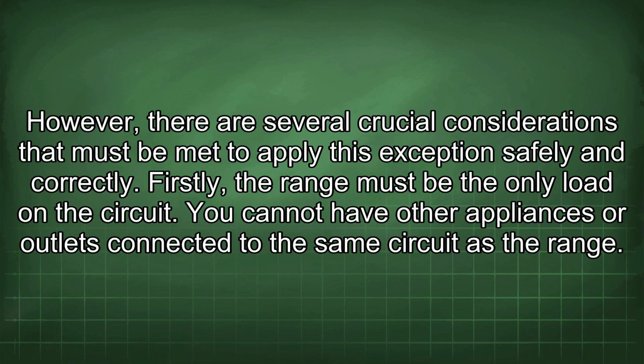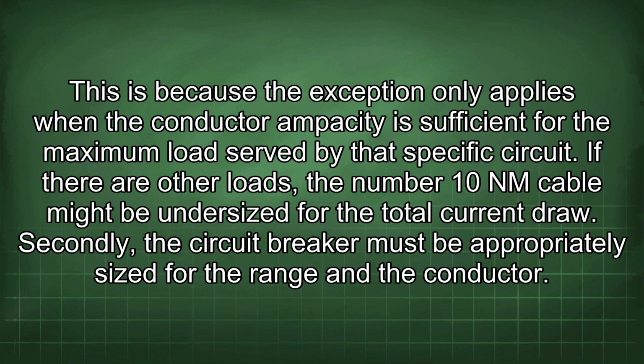However, there are several crucial considerations that must be met to apply this exception safely and correctly. Firstly, the range must be the only load on the circuit. You cannot have other appliances or outlets connected to the same circuit as the range. This is because the exception only applies when the conductor ampacity is sufficient for the maximum load served by that specific circuit. If there are other loads, the number 10 NM cable might be undersized for the total current draw.